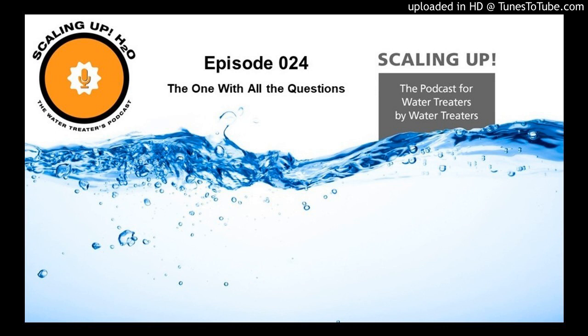Now, when you're going to put the boiler back online, you need to calculate how much water is going back into the boiler. And all of your products out there have a dosage rate. And what you're going to do is, if it's so many 100 gallons, you're going to figure out what the dosage rate is for that so many 100 gallons and actually put that directly right on top of the boiler and bring it up. A lot of people will assume that their chemical feed pumps are going to bring that boiler back up to where it needs to go. And those chemical feed pumps, they are there to maintain what is there. So once you're done with the boiler inspection, you're filling it back up with water, you've got to get it up to what you want to maintain.